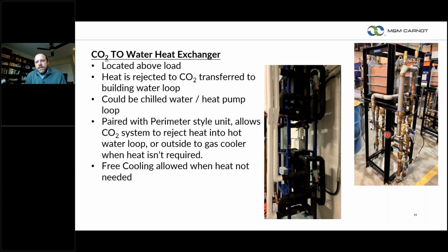So one of the things I think is unique is the CO2 to water heat exchanger. One of the things that we're looking at in the future, and what some of our customers and partners have asked us to do, is to create a perimeter style cooling unit, which can range anywhere right now between 15 and 48 tons worth of cooling. Those are our standard building blocks. We're always looking to do something bigger, but the idea is you have an indoor perimeter style unit sending heat, or sending that hot gas, up to your gas cooler.